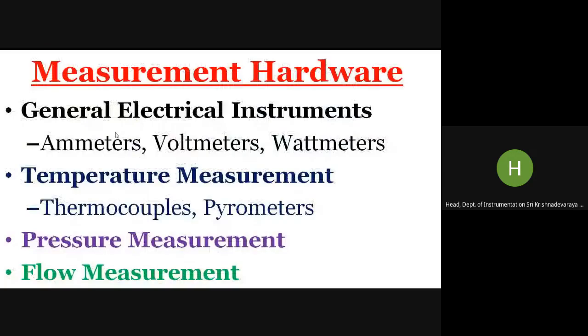The measurement hardware used generally includes electrical instruments such as ammeters, voltmeters, and wattmeters. In the electric arc furnace, you are measuring at 11 kV and 10,000 amps — a very different scale from laboratory milliamps and microamps. Voltmeters here measure in kilovolts and wattmeters in kilowatts. Temperature measurement is done primarily through pyrometers and thermocouples, and pressure measurement is also employed.